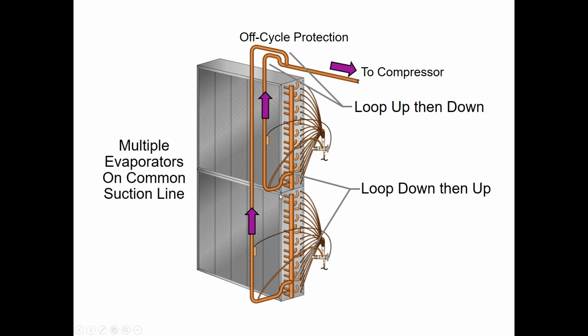Now there's what's called split face, and that would be if this coil was running independent of the top coil. Usually, split face applications were something where there was some type of humidity process control. Other than that, there isn't any real comfort cooling practice or use for split face application. Because let's think about it. We're trying to cool and dehumidify the air, right?